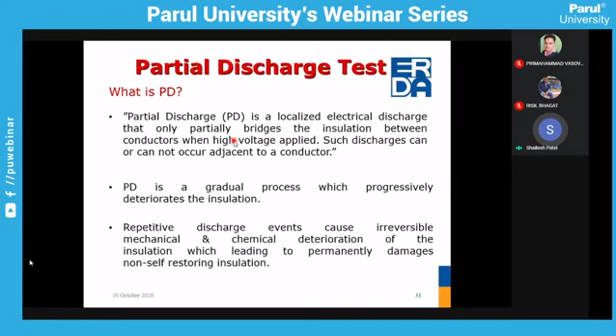One of the PD sources is there, and two dielectric materials are there. So this type of micro cracks will be generated by the PD source, and ultimately you can see the overall good insulating material is reduced by these micro cracks, and dielectric strength is reduced, and unwanted breakdown of insulating material occurs. So this is the importance of cables, and we need to carry out the partial discharge test.